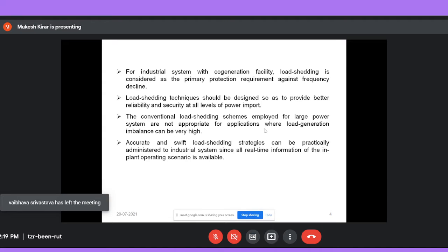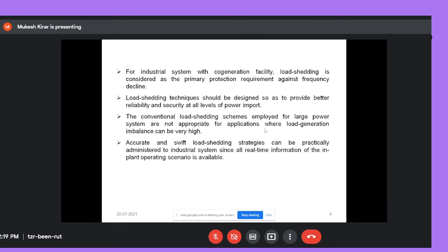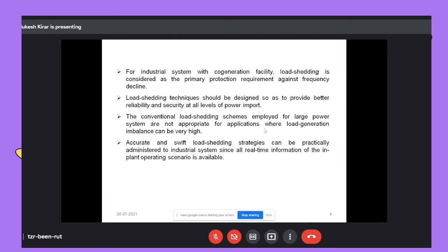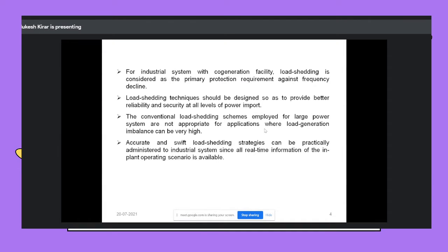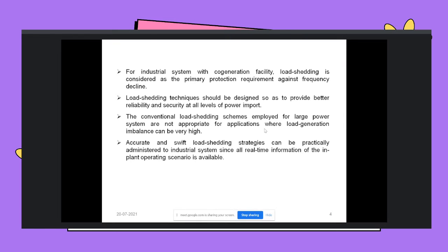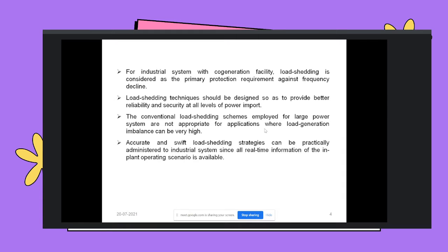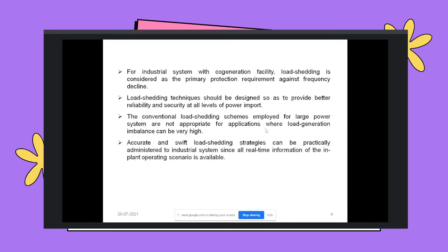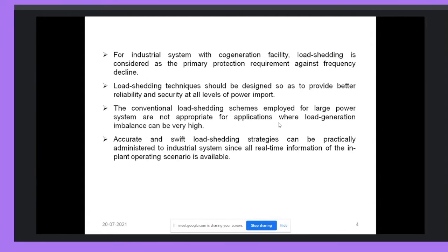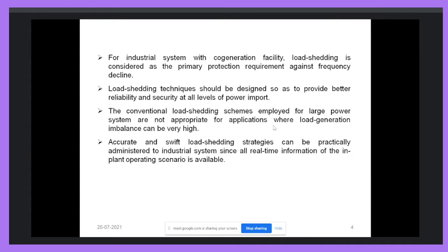Similarly, we can relate active power balance and frequency. Whenever there is an excess of generation and less load, there will be a problem of over frequency, because if active power in the system is more than the load, the system will have an over frequency problem. If the system has a greater load as compared to the generation, frequency will decrease. So an industrial system with cogeneration, meaning its own in-plant generation, if separated from the utility grid, has to match load and generation exactly. Otherwise, there will be a frequency stability problem.